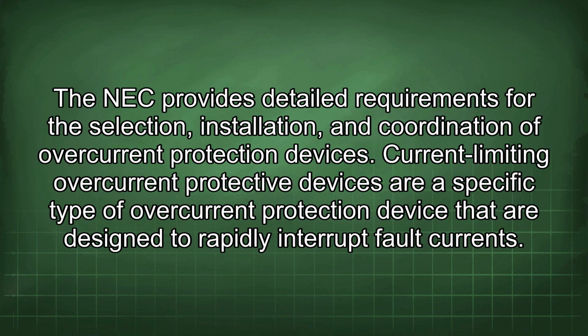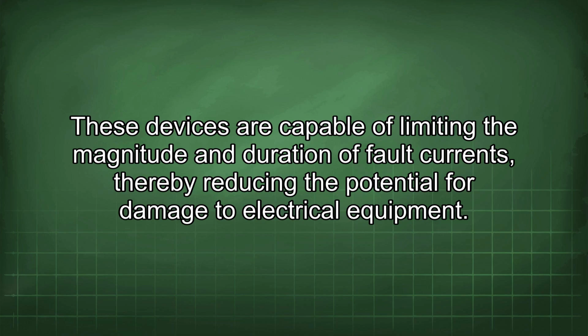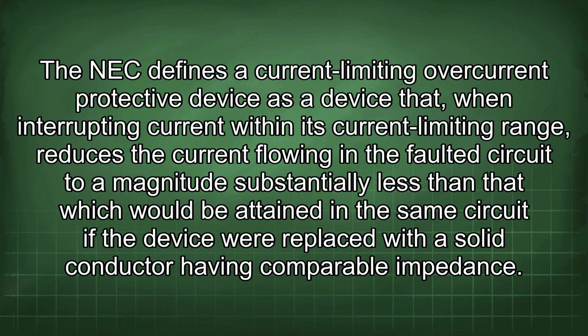The NEC provides detailed requirements for the selection, installation, and coordination of overcurrent protection devices. Current-limiting overcurrent protective devices are a specific type of overcurrent protection device that are designed to rapidly interrupt fault currents. These devices are capable of limiting the magnitude and duration of fault currents, thereby reducing the potential for damage to electrical equipment. The NEC defines a current-limiting overcurrent protective device as a device that, when interrupting current within its current-limiting range, reduces the current flowing in the faulted circuit to a magnitude substantially less than that which would be attained in the same circuit if the device were replaced with a solid conductor having comparable impedance.